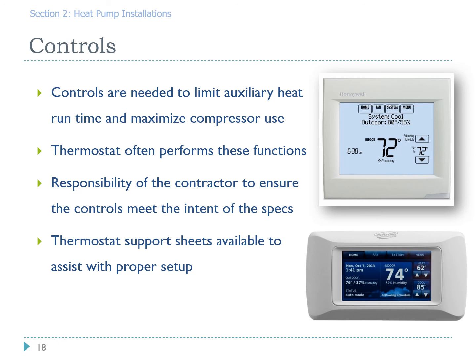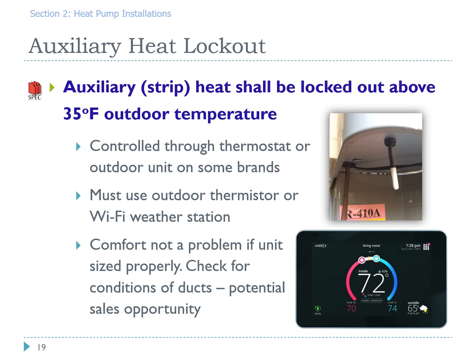Now we'll discuss controls. Controls are needed to limit auxiliary strip heat runtime and maximize compressor use. These functions are typically set up through the thermostat, and the technicians have the responsibility to meet those specs. We've created a lot of thermostat support sheets that are available to assist with proper setup. These support sheets go into proper auxiliary strip heat control lockouts, compressor lockouts, and test modes to be able to commission the system properly.